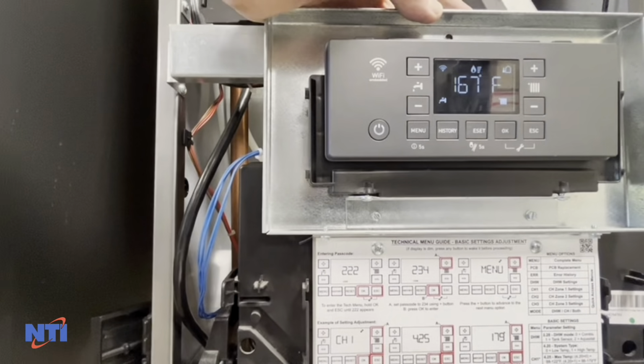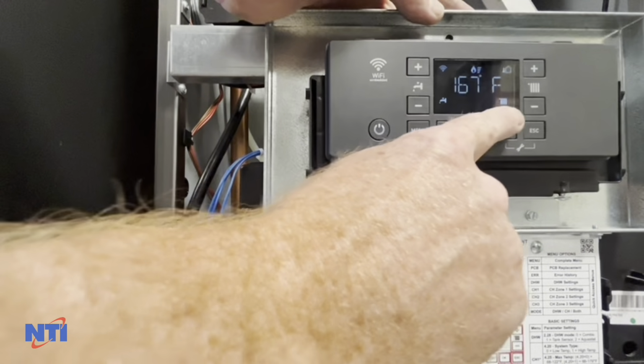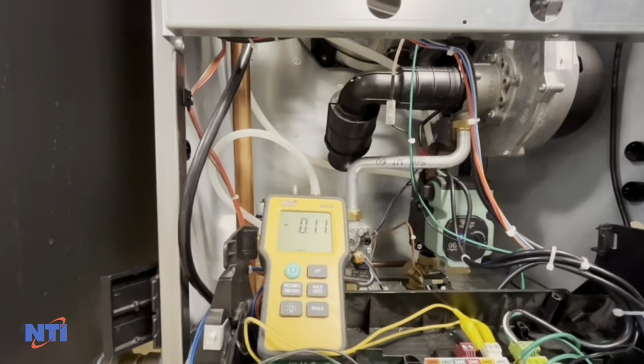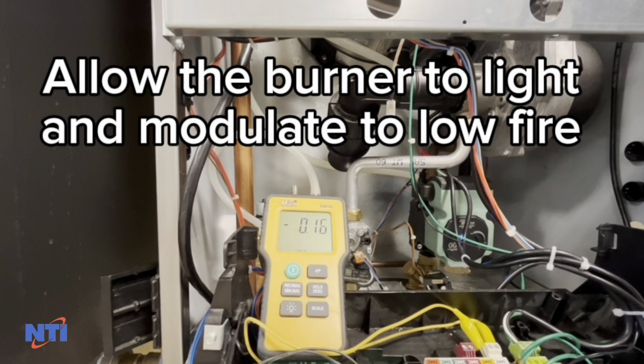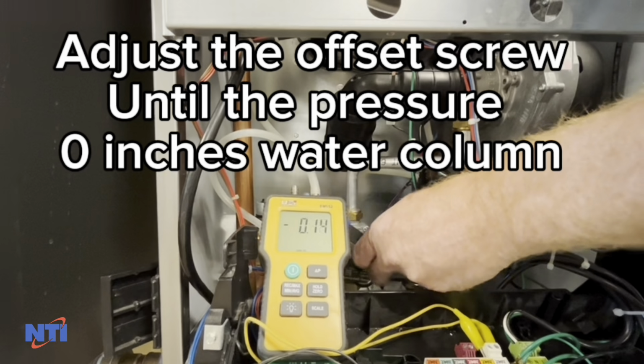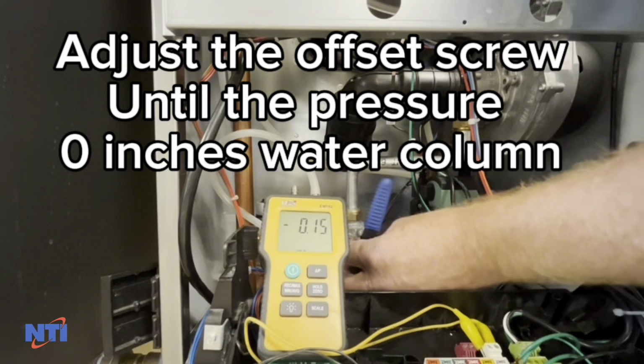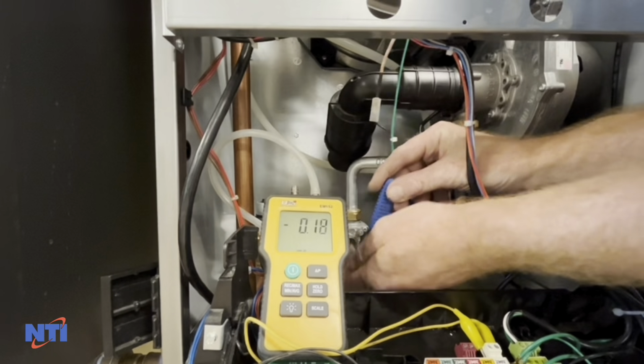Allow the boiler to modulate to minimum fire. Then, using the adjustment screw, set the gas pressure to 0 inches water column. Clockwise turns will raise the pressure, counterclockwise turns will lower the pressure.